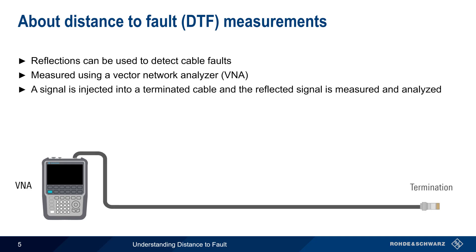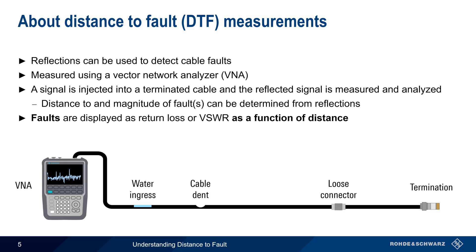These reflections can therefore be used to detect cable faults. This is done using an instrument called a Vector Network Analyzer, or VNA. Since this measurement is often made in the field, portable or battery-powered VNAs are most commonly used. A signal is injected into a terminated cable under test, and the resulting reflections are measured and analyzed to determine both the distance to, as well as the magnitude of, any faults along the cable. These faults are displayed in terms of return loss or VSWR as a function of distance, and therefore this measurement is referred to as distance to fault.